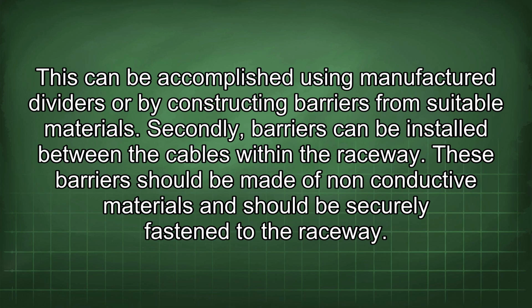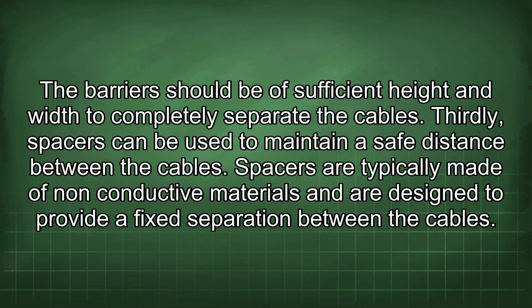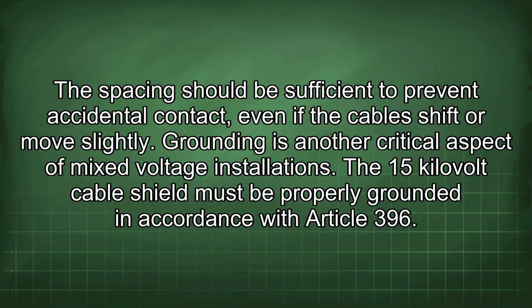Secondly, barriers can be installed between the cables within the raceway. These barriers should be made of non-conductive materials and should be securely fastened to the raceway. The barriers should be of sufficient height and width to completely separate the cables. Thirdly, spacers can be used to maintain a safe distance between the cables. Spacers are typically made of non-conductive materials and are designed to provide a fixed separation between the cables. The spacing should be sufficient to prevent accidental contact, even if the cables shift or move slightly.